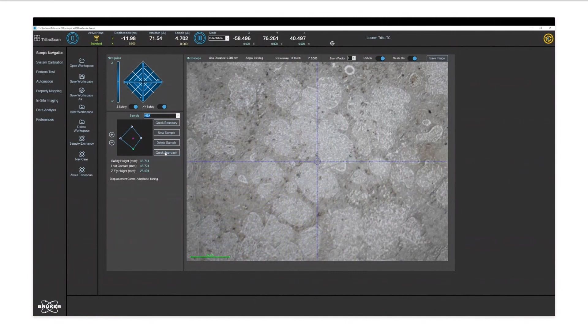Now let's go into imaging approach where the scan settings can be defined and the sample can move to be under the piezo transducer setup to scan the surface of the sample. There are a number of imaging parameters to optimize the size and speed of your scan.